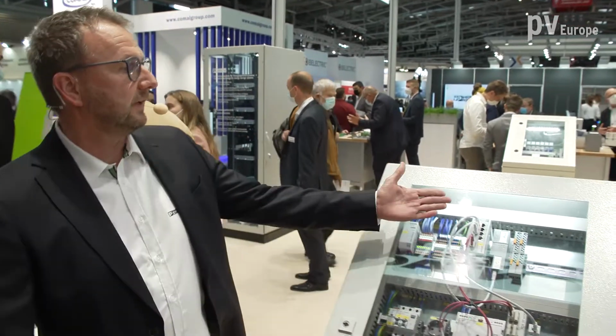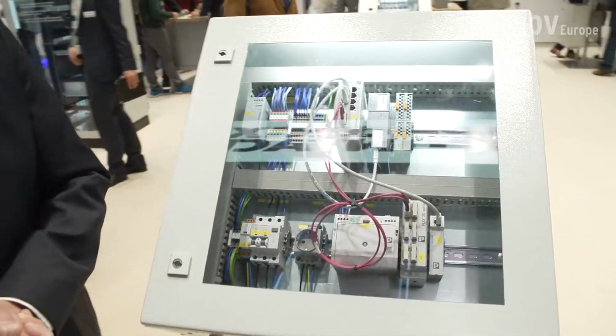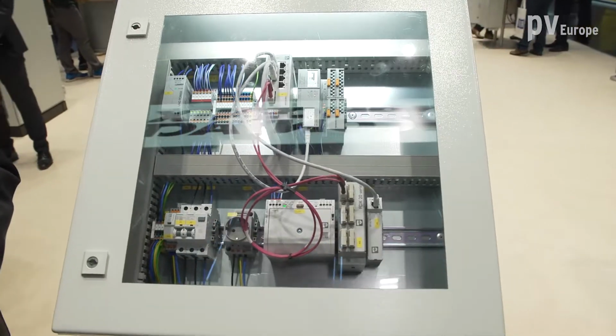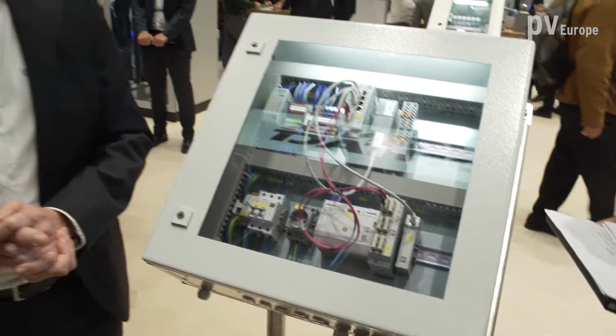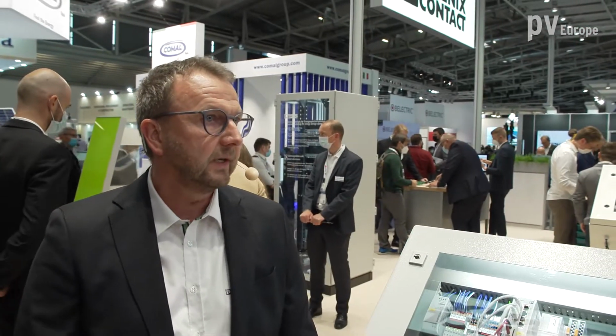Which product do you present today? Today I want to present our new power control unit based for the German grid codes. If you want to feed power more than 135 kilowatt into the grid on the medium or high voltage level, you have to have a certified solution. And that is our PCU, or power control unit.